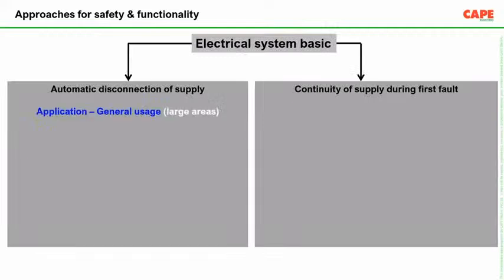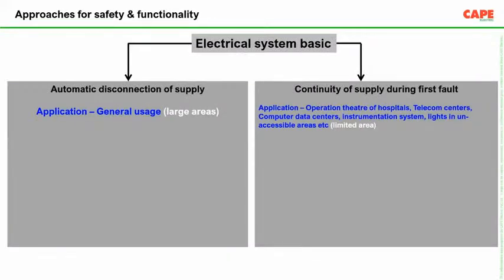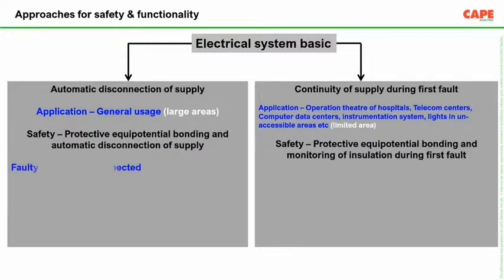So here, the earthed system and unearthed system. In an earthed system, safety is achieved by automatic disconnection of supply. That means the supply should trip as quickly as possible. Whereas in the case of the unearthed system, safety is achieved by protective equipotential bonding and monitoring of insulation during the first fault. Monitoring of insulation is done by insulation monitoring devices. So there is a device called the insulation monitoring device. You should connect this device between all the current carrying conductors and the earth. Earth means the metallic parts of that particular building. So as a result, whenever there is an insulation failure, this device will give you an alarm.